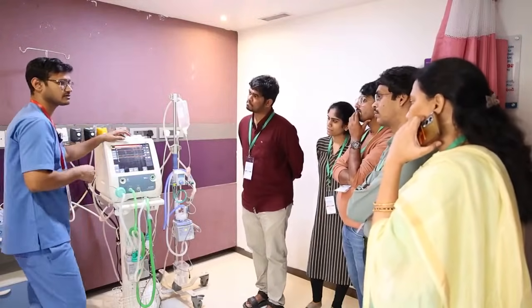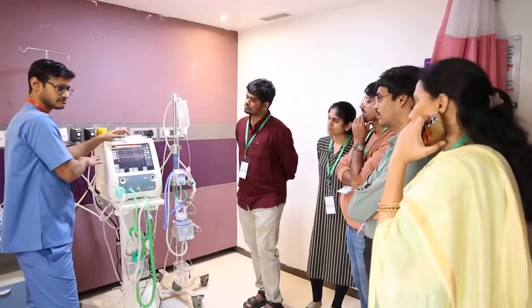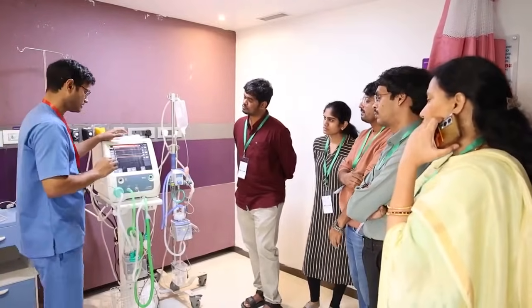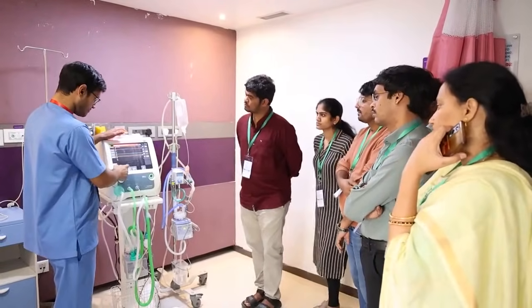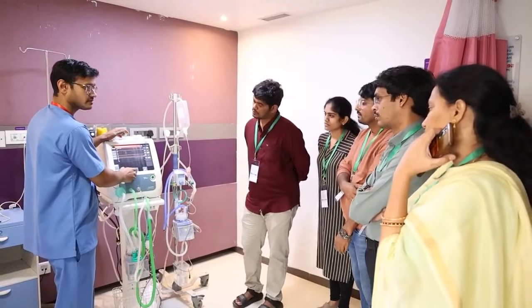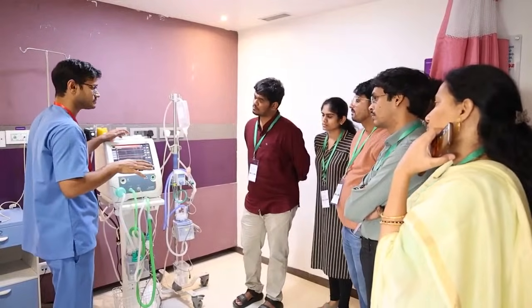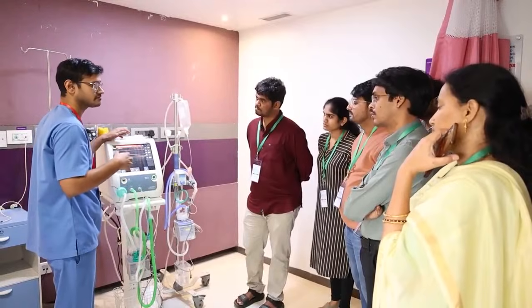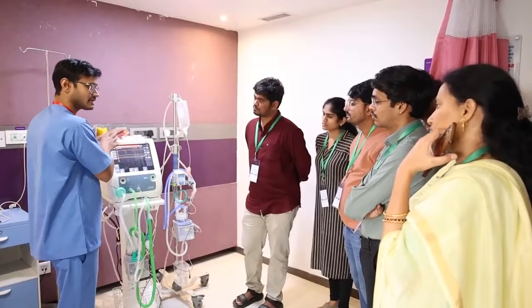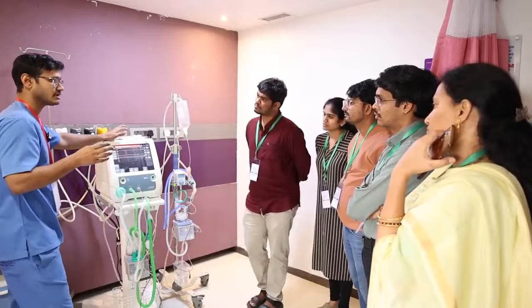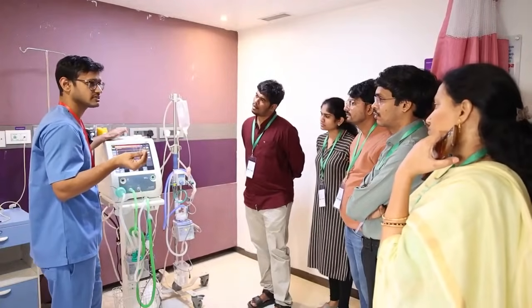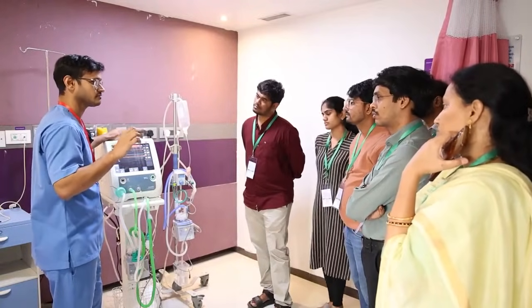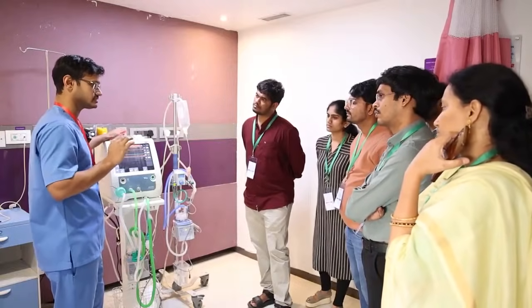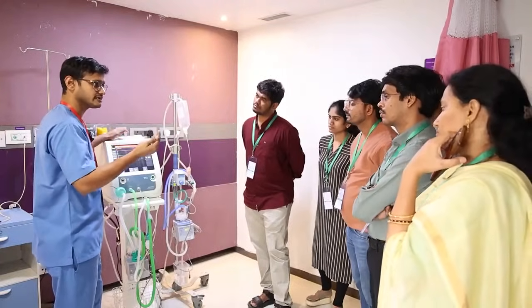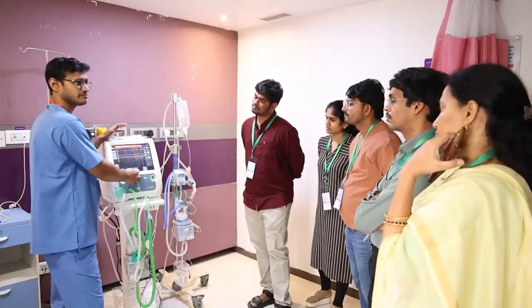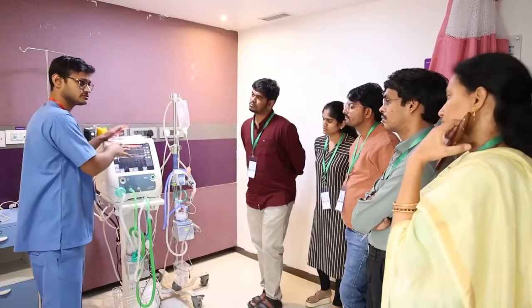In the SLE we cannot adjust the flow. It comes as an inbuilt thing in the SLE. Flow adjustment is not there. But one additional parameter is this PIP. In CPAP we don't give PIP, but this is for the backup. Suppose the baby goes into apnea, we will have an apnea alarm limit which is set. If the alarm limit you have kept as 15 seconds or 20 seconds, and if the baby doesn't take a breath for 15 or 20 seconds, the ventilator detects it as apnea, and then it gives an additional PIP on PEEP for the rate which you set as the backup rate.